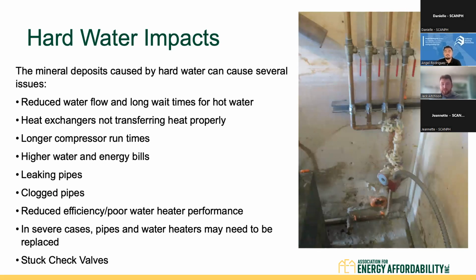The most vulnerable systems to hard water are tankless water heaters. When they first were rolled out, we had a lot of issues with hard water affecting these tankless water heaters. Heat pump water heaters are in a similar category as tankless because they have such small flow paths that the water has to pass through. It's really easy for them to get clogged. However, you're not going to experience the significant failure that you saw with tankless water heaters, where the whole water heater had to be replaced. You may need to replace components of the heat pump water heater. However, that's expensive, and it's much easier to include in your maintenance plan mitigating and preventing hard water and calcium and magnesium bicarbonate buildup in the heat pump water heater itself.